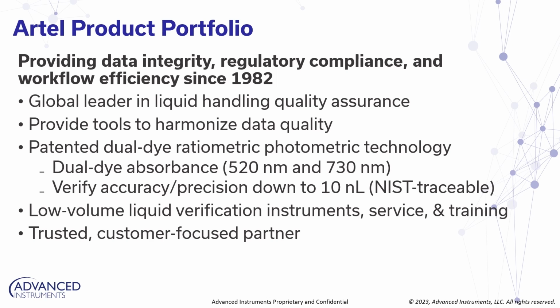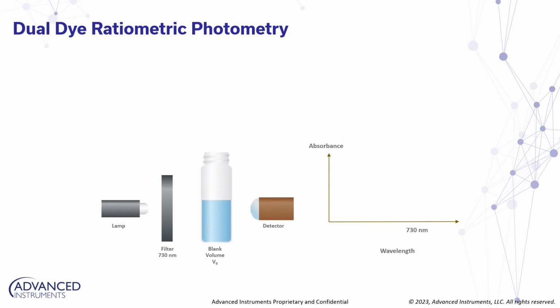The technology and solutions are part of an unbroken chain of traceability from 5 mL all the way down to 10 nanoliters. In this example, you can see that we begin with a vial filled with a blue dye. Absorbance is measured at 730 nanometers. Then the sample is added, which is a red dye. This is the volume of interest. The two solutions are mixed together. And finally, the absorbance is measured at 520 nanometers. The software then calculates the volume of interest.